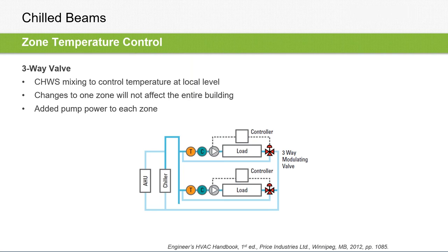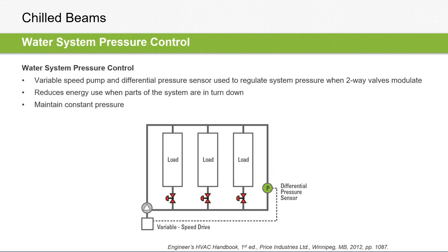So it's a good way to keep that individual zone controlled. For example, if you have two different zones that are next to each other, and they both have operable windows, but one's open, one's closed. With this recirculating zone water, you can keep that water temperature above dew point, even if the window's open and the moisture's coming in. You can control the water temperatures of each zone individually. So that's a pretty cool feature if you're really worried about condensation, or you have a dormitory or something like that, where you're not going to be able to control the windows in that space. That's an interesting way to run this. You would need a pump within that space as well.